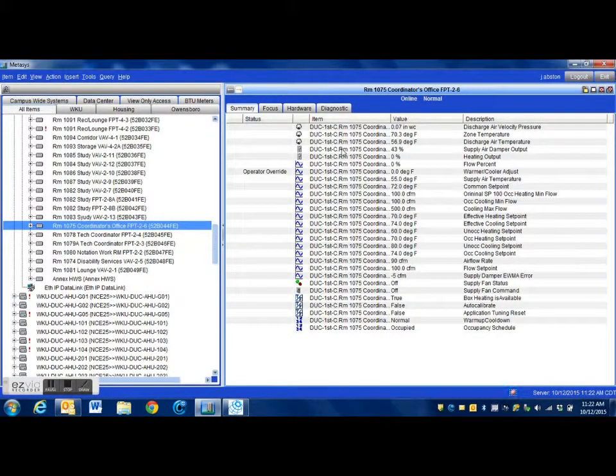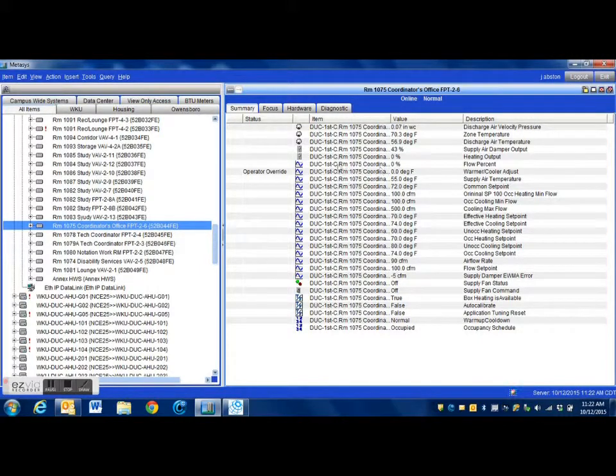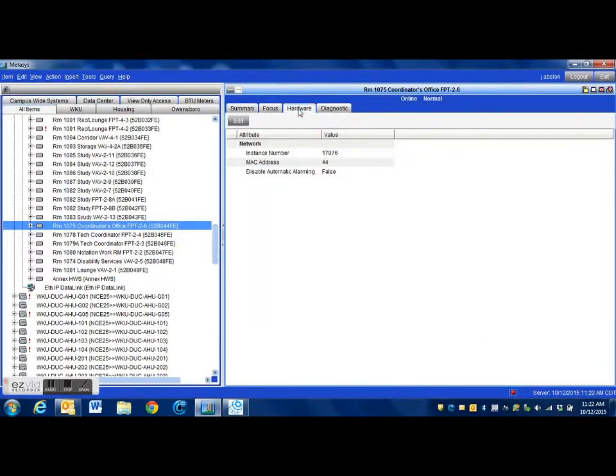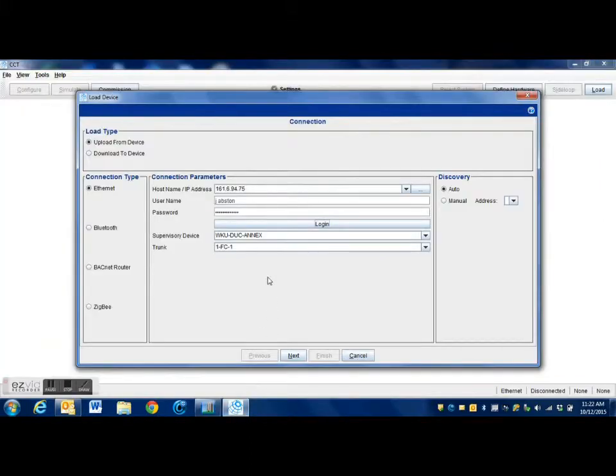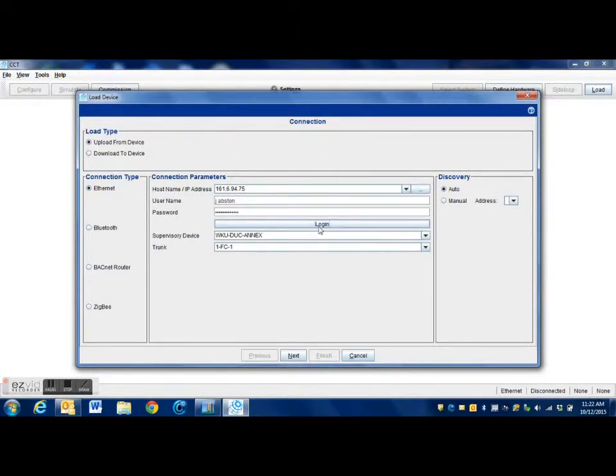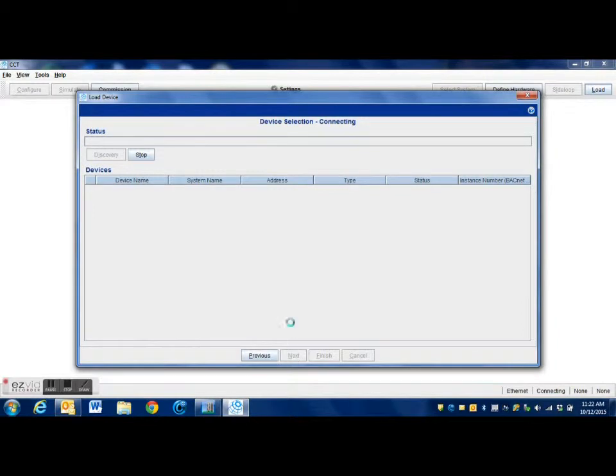Using a control point that we will add to the VAV control program that utilizes the occupancy override. The first thing we do is determine the address for the VAV, so we're going to load the program from the VAV into the controller configuration tool.